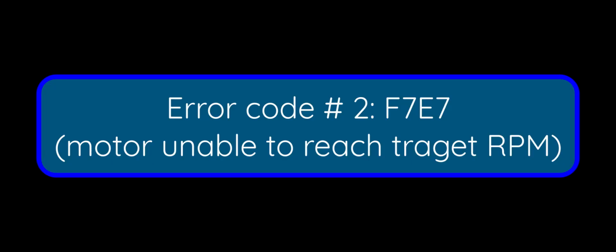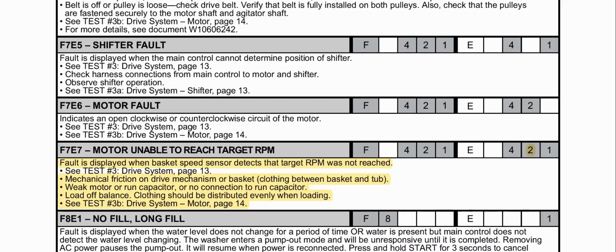Alright, what you're looking at is page 7 of the service manual. We're dealing with error code number 2, which is F7E7, and that means the motor is unable to reach target RPM. So what it says here is the fault is displayed when the basket speed sensor detects target RPM was not reached.